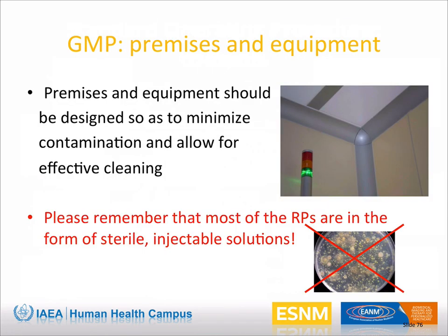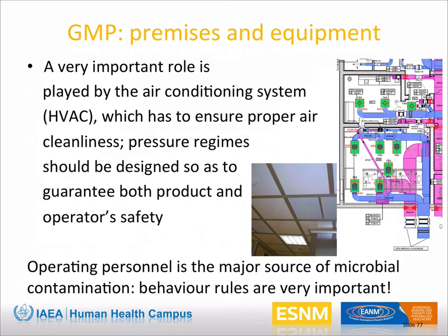GMP defines characteristics and requisites for premises and equipment, which should be designed so as to minimize contamination and to allow for effective cleaning. This is very important if we remember and consider that most of the radiopharmaceuticals are in the form of sterile injectable solutions, so microbial contamination has to be kept at a minimum extent.